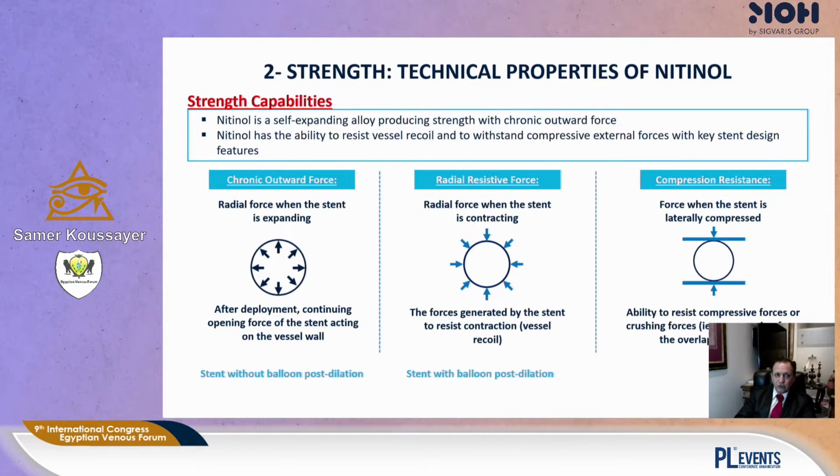That is the reason why nitinol is more common than steel in the venous system. It has the ability to resist vessel recoil and withstand compression and external forces, which is the main key design feature of the nitinol stent in the venous system.